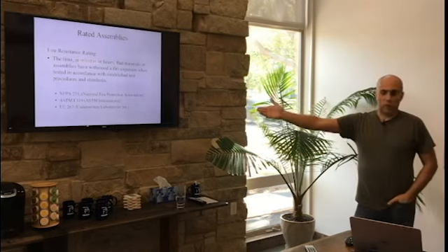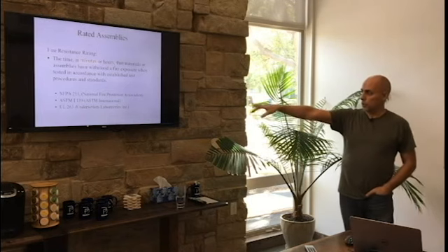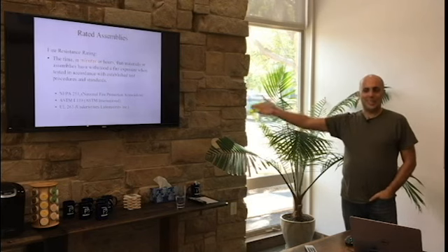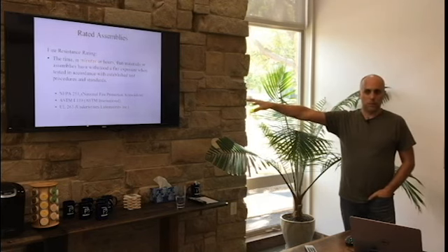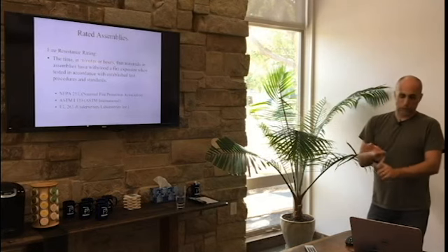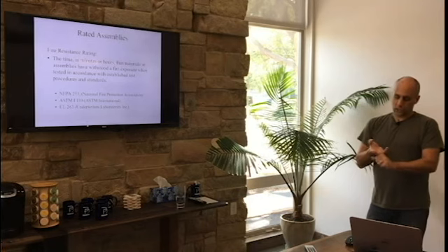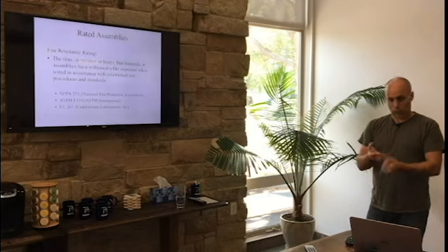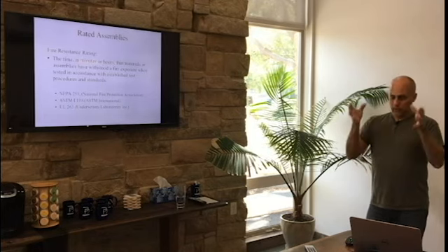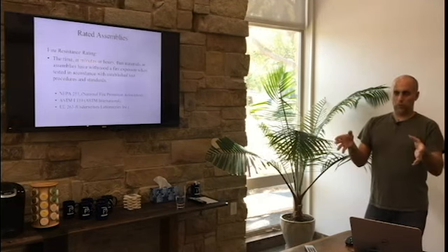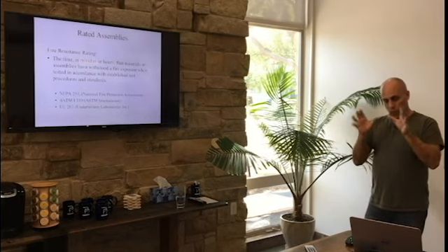One is an NFPA standard, which is really being phased out because the other 2, ASTM E119 and the UL one, are more heavily used now by any testing agency. They all have the same requirements. If you test something per it, you're going to go to UL, you're going to pay your thousands of dollars, you're going to say, this is the assembly we want. This is how big it is. These are the components. These are the exact products. This is how far apart we want the screws. This is how long the screws are. They build it, put it in the furnace or above the furnace, depending upon what kind of assembly it is, and they burn it. And they say, we want it to last 1 hour.